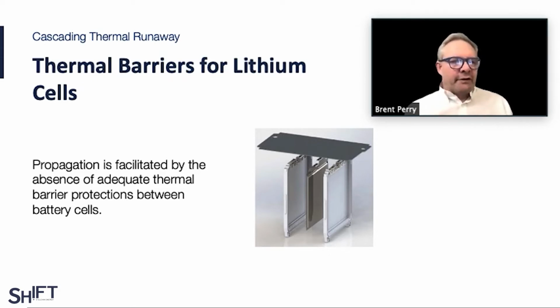A lithium cell can reach a temperature of 1,000 degrees on a spontaneous eruption, and that's something plastic is going to have a very hard time managing. So we have gone down the road now of using metal cell carriers with metal barriers between, with about a 2 millimeter space at the top of the cell to prevent propagation from occurring if a cell does catch fire and explode.